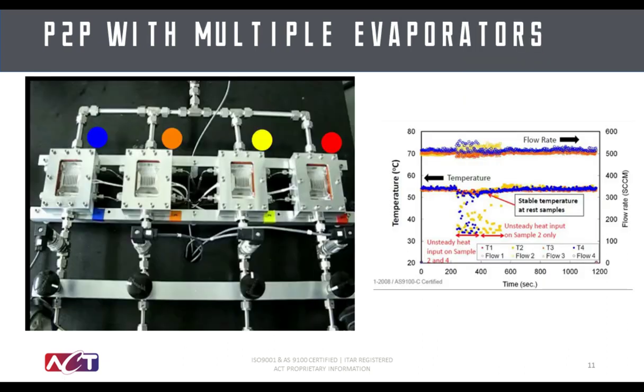Here's a video demonstrating pumped two-phase cooling with multiple evaporators. In this test setup, flow is entering the cold plates from the bottom. And what we're showing on the video are 4 independent cold plates with their heat loads turning on and off. All of the cold plates are serviced by the same pump and the same manifold on both the upstream and the downstream portions of the system.